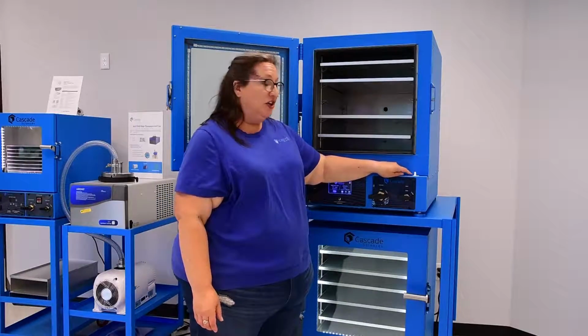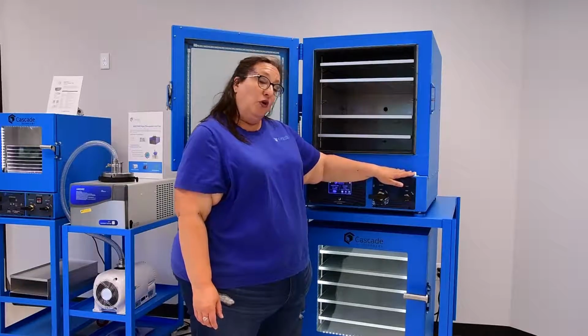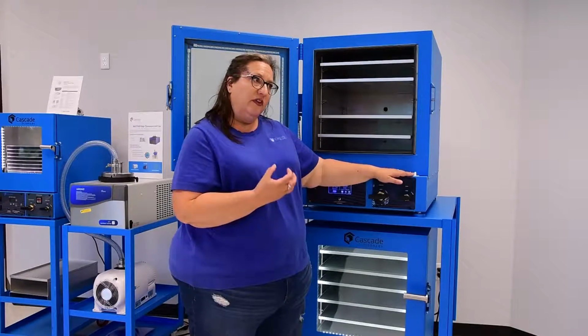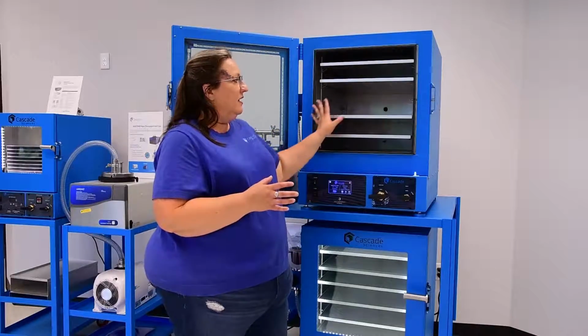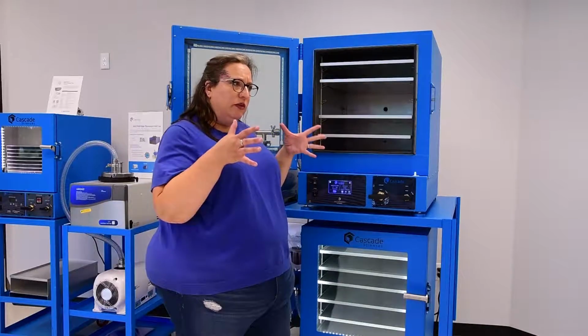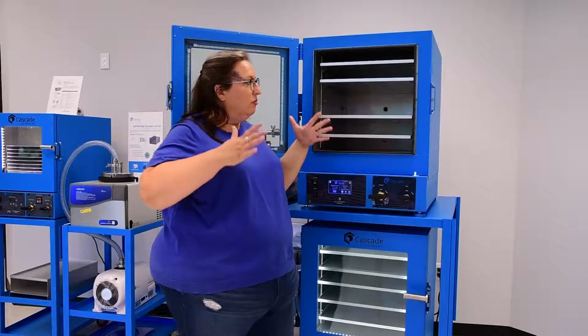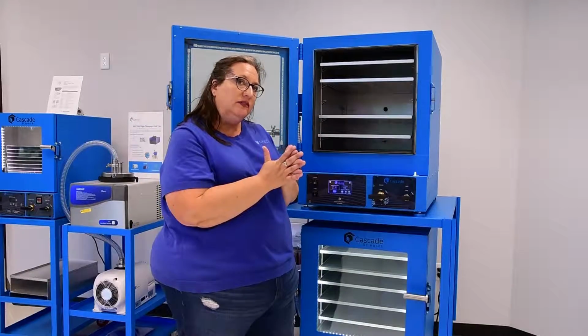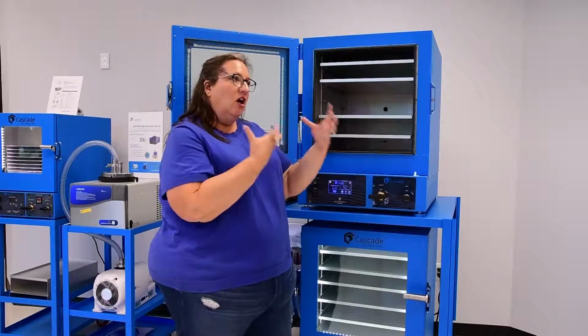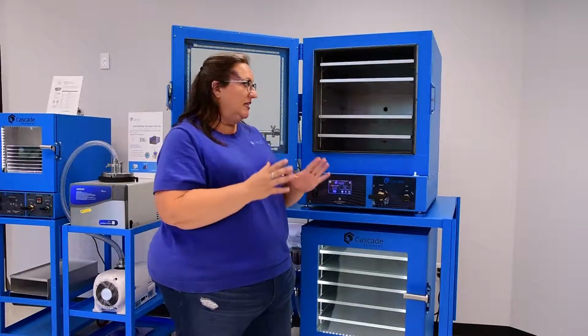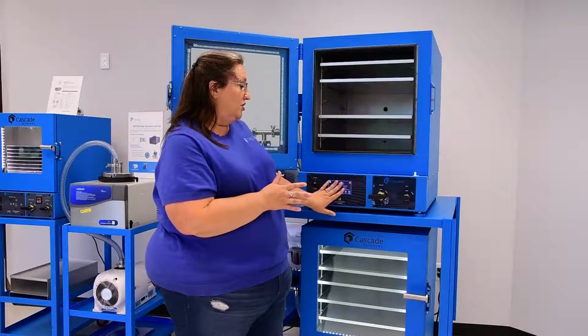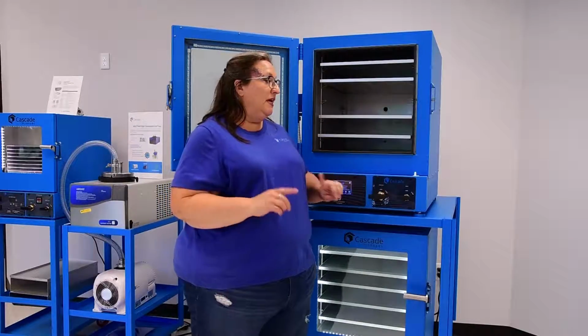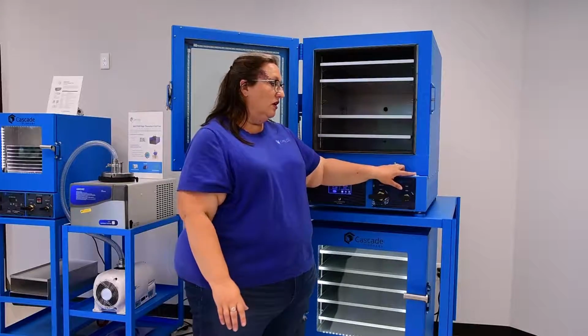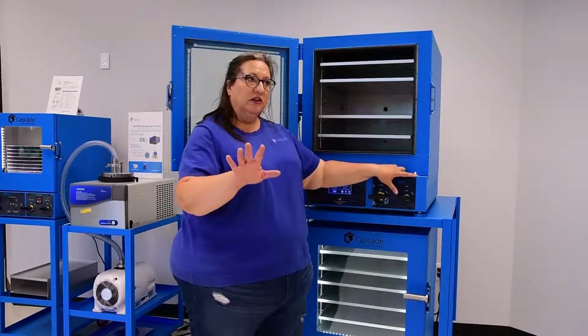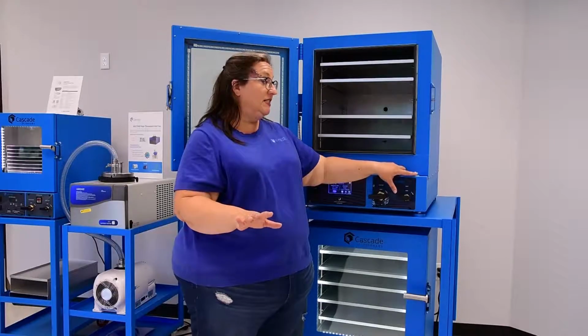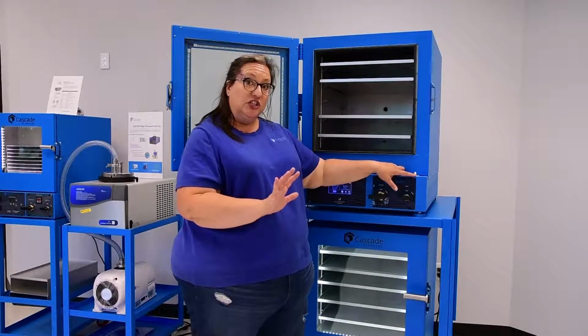This is the door switch. When you open up the door or you backfill the oven, it's going to cause a temperature spike. The oven will be nicely heated under vacuum. The walls will be nice and warm, developing thermal mass to transfer across the shelves. And when you backfill with air, all that atmosphere touches the walls, conducts heat, and you might see a temperature spike, which could be upsetting to the controller. Because we're going to backfill and open the door, this switch will tell the controller, don't worry about the temperature for about 10 minutes. We're opening up the door, just be still.